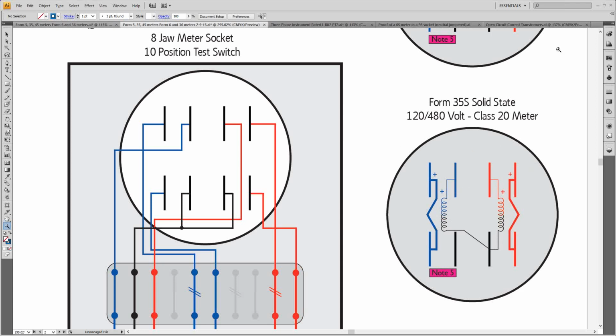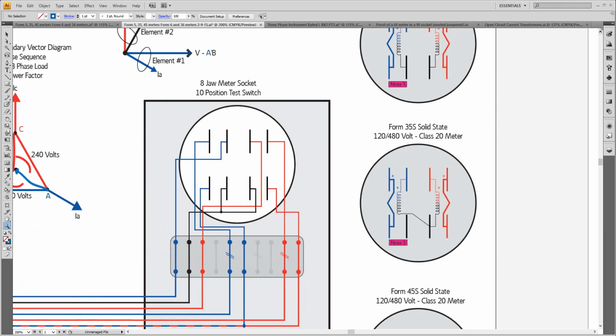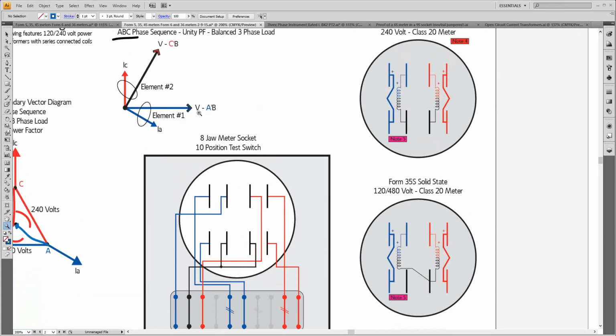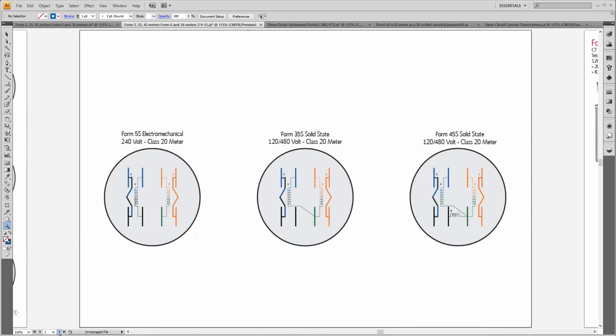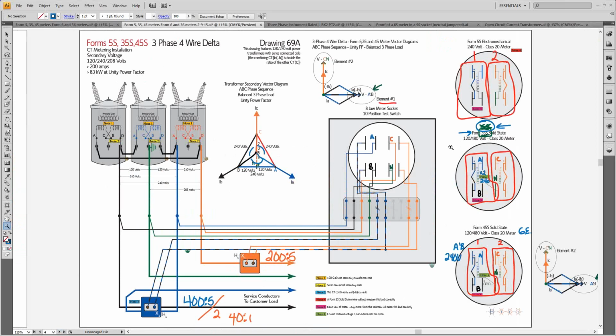As we look at the vector diagram for this one, zoom out just a little bit, maybe to 200, the voltage across A to B is 240 volts, C to B voltage is 240 volts, A to B across there, C to B across there, and so that's how the 35S fits with the 3-wire delta as opposed to the 45S on the 4-wire delta. Does that make sense? Any questions?